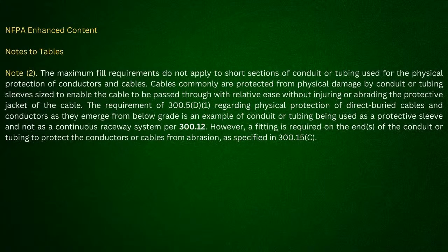Yeah. And when I've been out on the job, and we put a sleeve in, this is just the way we were taught. A sleeve was never more than 10 foot, period. In other words, you could never go longer than a length stick of conduit. That's the way we were taught. Right. And there were no fill requirements, anything. There wasn't any reduction of any conductors for any type of correction factors, adjustment factors, anything. Because what they looked at is, one end's open and therefore the heat can escape.